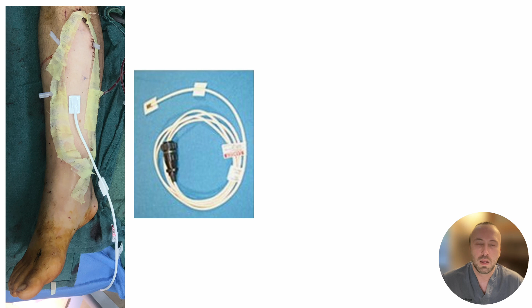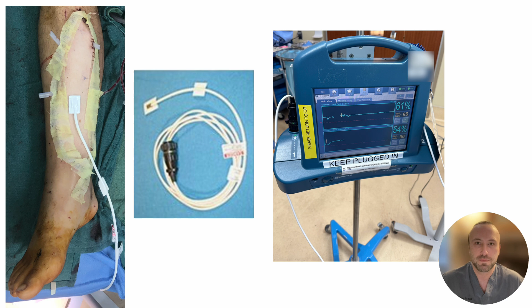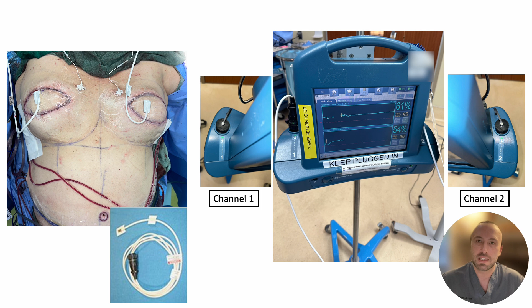The sensor probe is attached to a fiber optic cable leading to a sensor head. This sensor head then attaches to the ViOptix monitor via a connector channel. The ViOptix monitor typically comes mounted to a wheeled stand for mobility. The sensor head attached to the sensor probe connects to one of two channels on the ViOptix monitor. The two channels can be used in cases of bilateral free flaps. These sensor heads are maintained connected at all times to provide continuous monitoring.